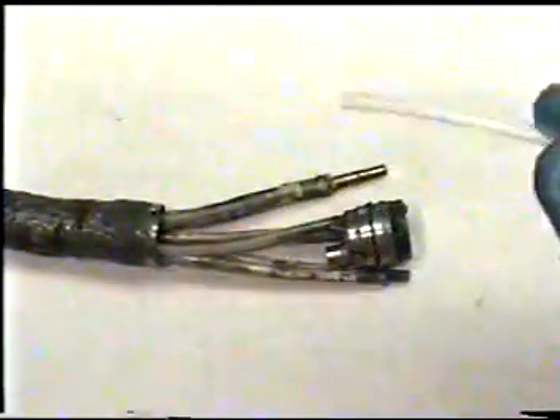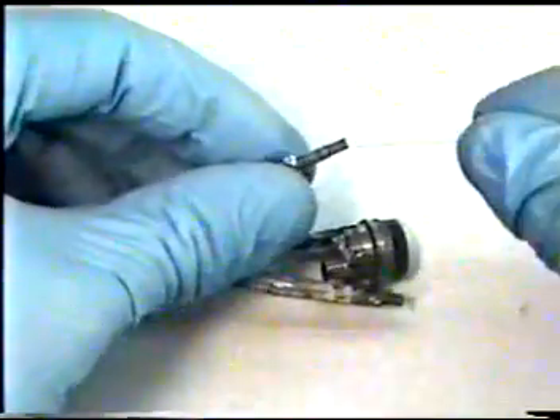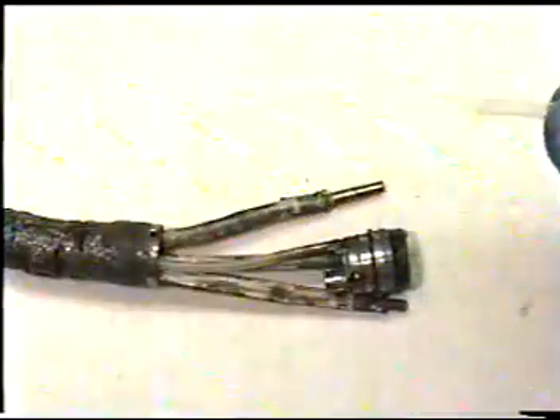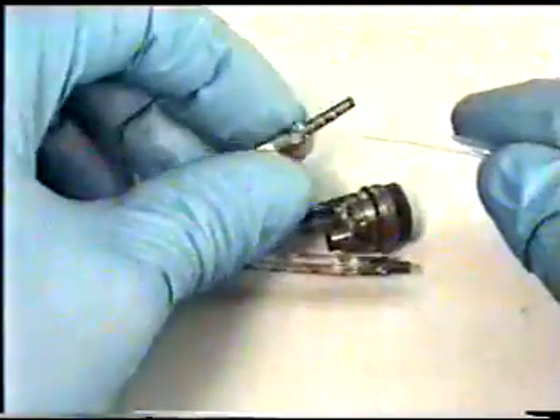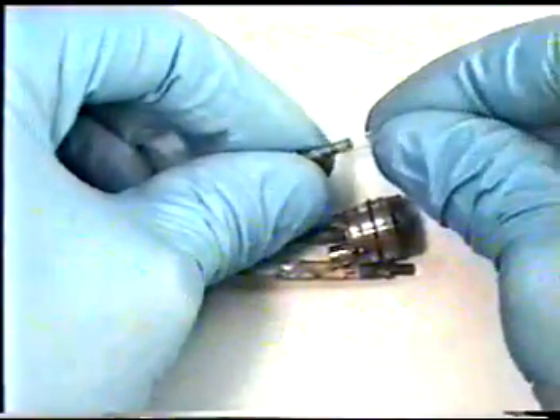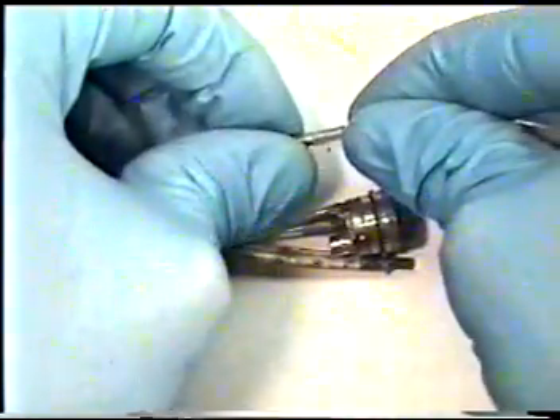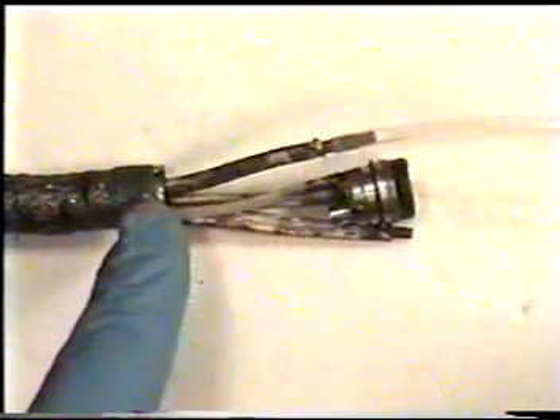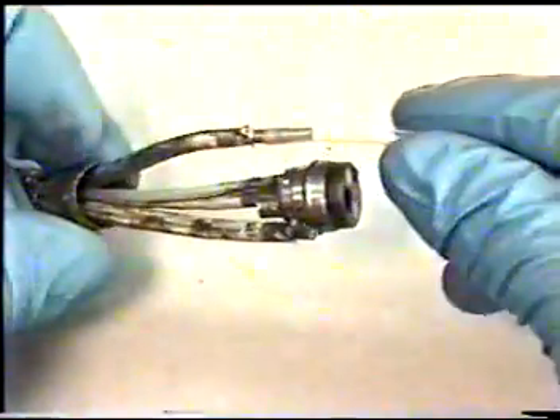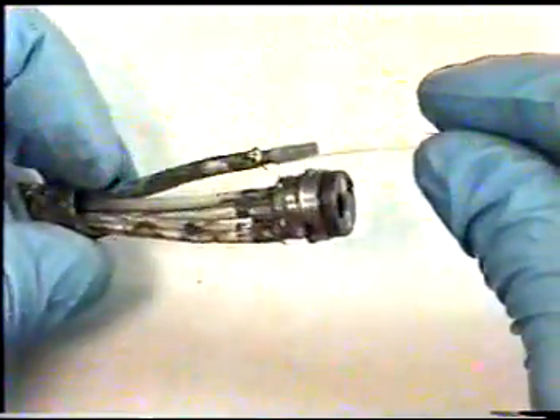Utilizing some plastic tubing, which is just slightly larger than your illumination light guide bundles, you'll need to slide the tubing over the old damaged illumination guide bundles in order to pull through the tubing when we pull through the old damaged light guide illumination bundles. This is in order to allow the new light guide to be pulled through in the correct position in your distal end. Each of the tubes, wires, and channels must be in a particular spot within the insertion tube and the bending section.